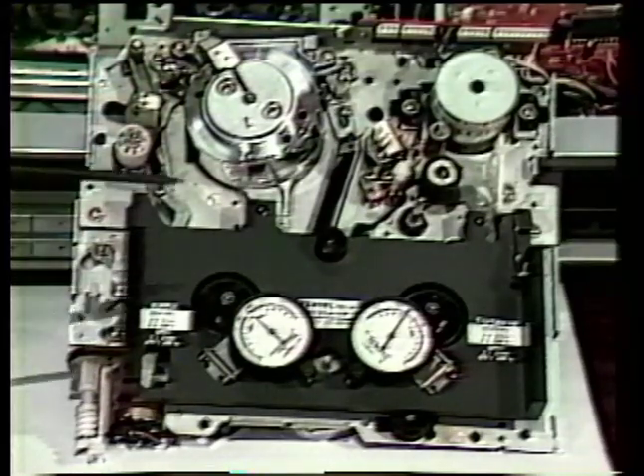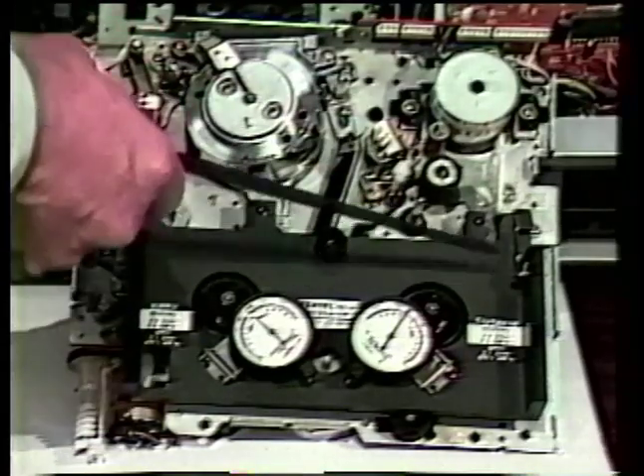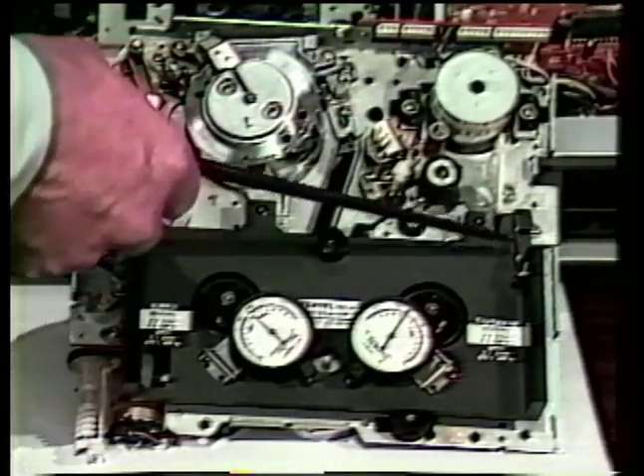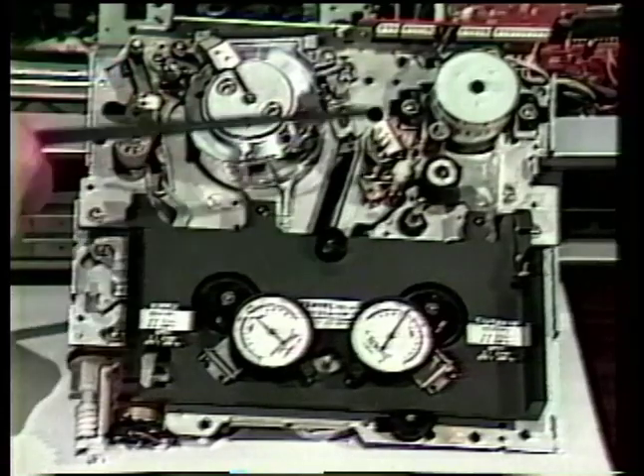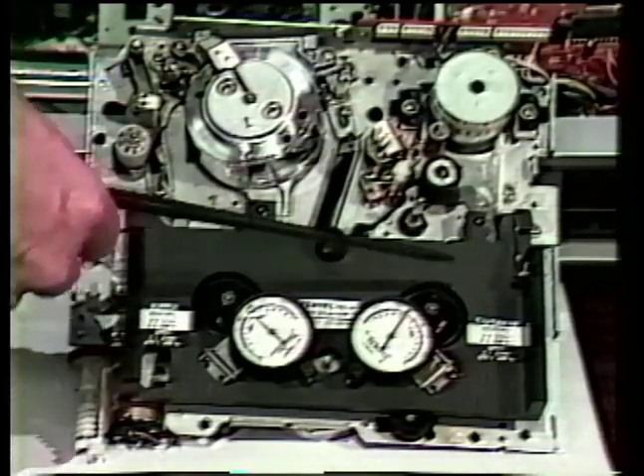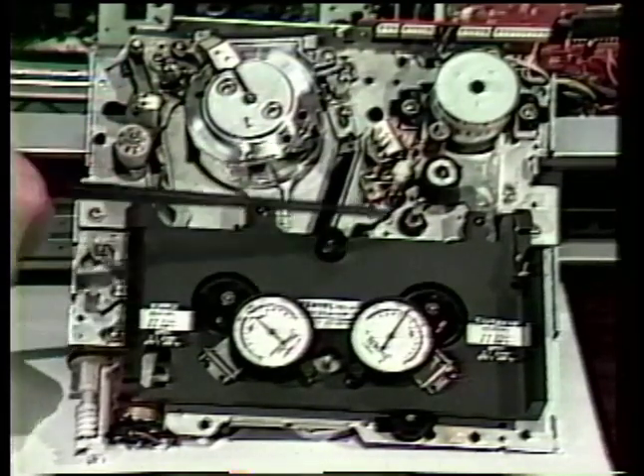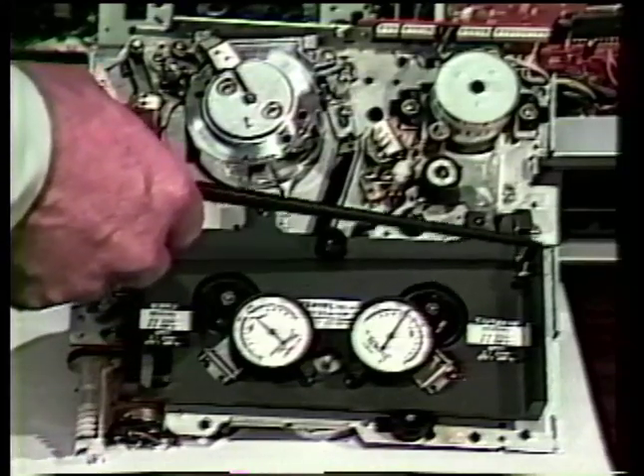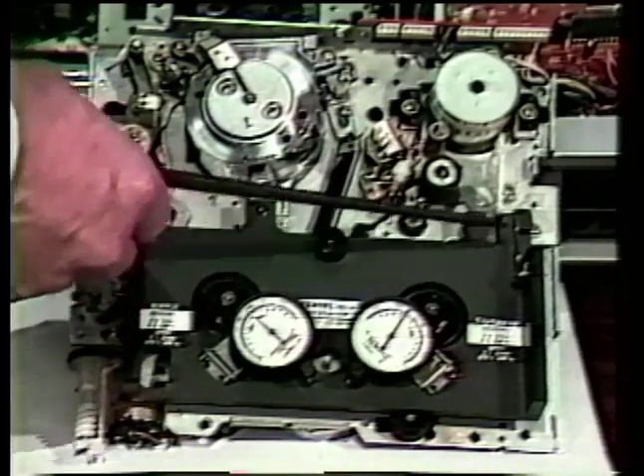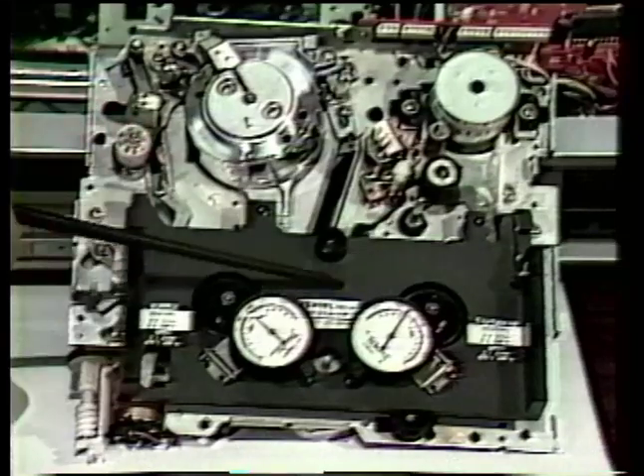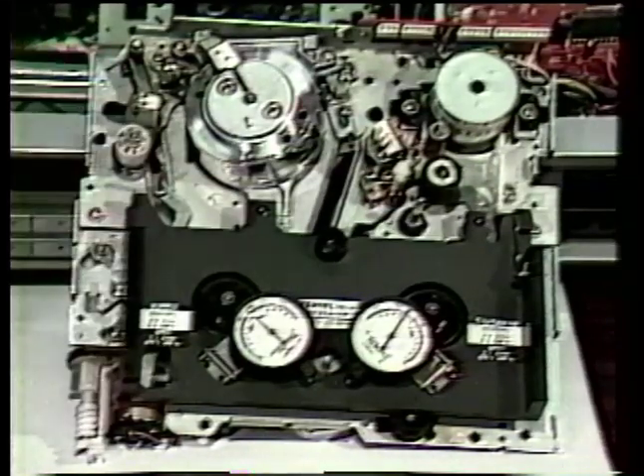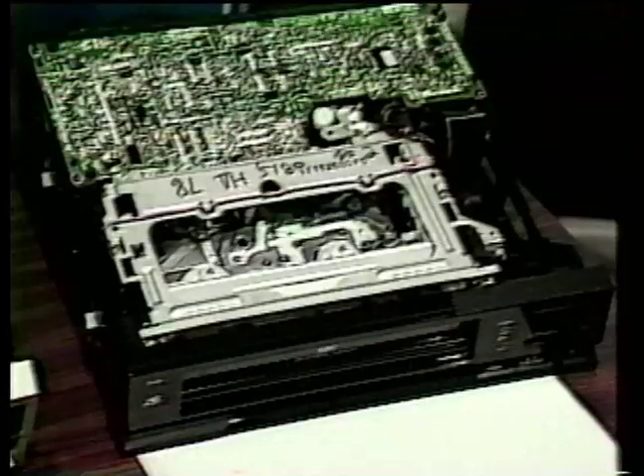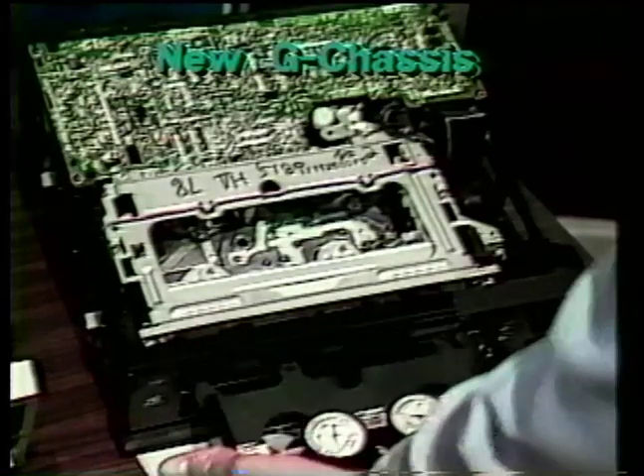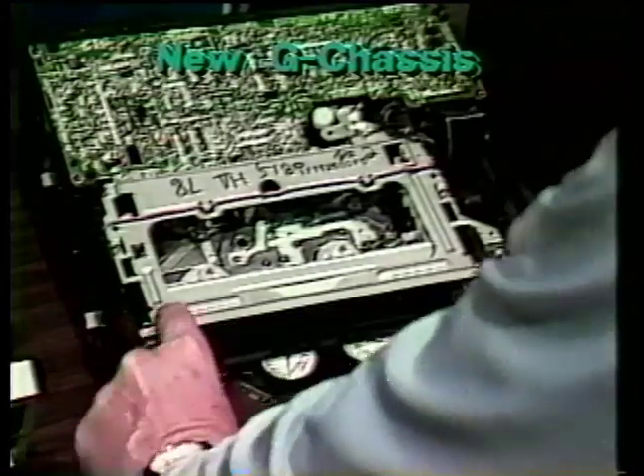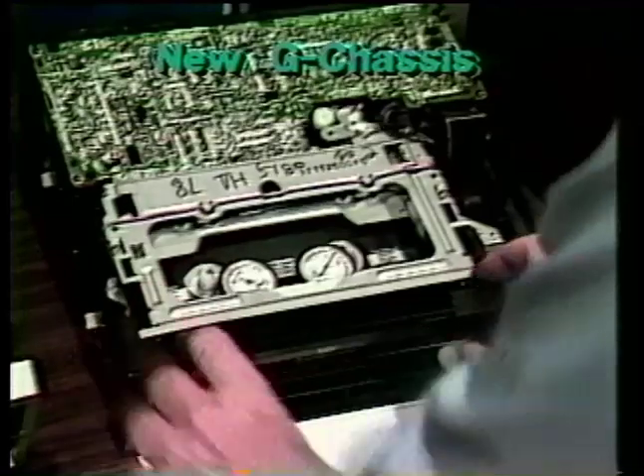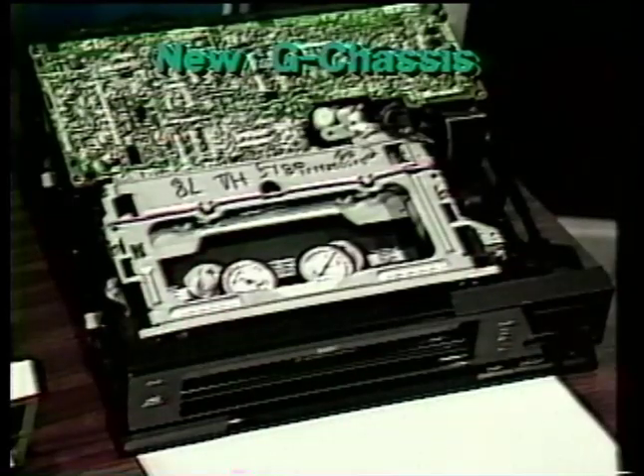It might be worth pointing out that many of these upgrades, what we try to do is design them in such a manner so that some of the old equipment in the field that we've produced before, even before this G chassis was available, can in fact be upgraded. And so just by replacing this side rail with this little lever, one of the older style gauges can actually be used on the new G chassis also. With this lever adapter, the gauge loads directly into a G chassis, just like a cassette.